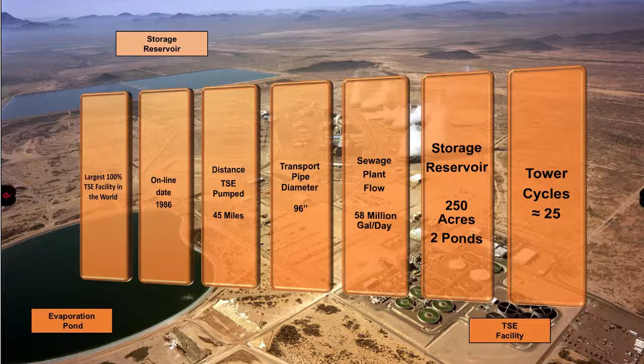Usually a cooling tower runs 1, 1.5, or 2 cycles. This one runs 25 cycles. By the time it's finished, you can literally take the blowdown as a solid and transport it to a landfill—it's that solid.